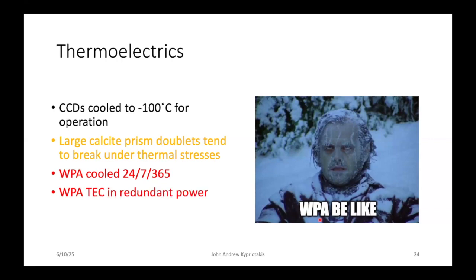And that's an extra reason that we need redundant power supplies and triply fail-safe them, is that if all power gets lost in the instrument, we essentially lose the entire instrument. Another feat is that it's impossible to non-destructively stop their cooling. You have to go and physically yank the cables out of the thermoelectric coolers if you want them to stop operating for the Wollaston prisms. And that's again because that's actually what's keeping the instrument alive at this point.